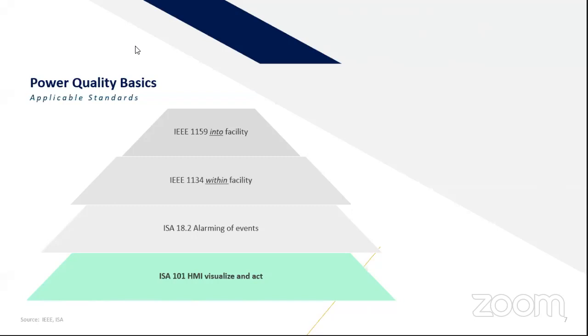So what we like to do is monitor the incoming power at the facility so we know what's actually coming in. Even if you have good power within your facility and you still have outages, sags, swells, and so forth, it may not always be your fault. The only way to know that is by looking at the power coming into your facility. Once it's in there, there's really nothing we can do about that incoming quality, but once it's in your facility, there are things we can help with, such as with drives, LED lighting, and for some of you, fluorescent lighting.